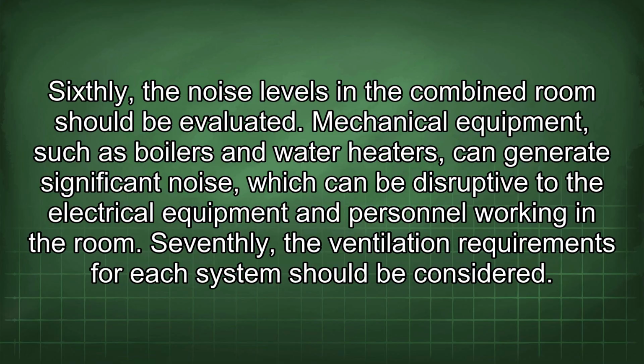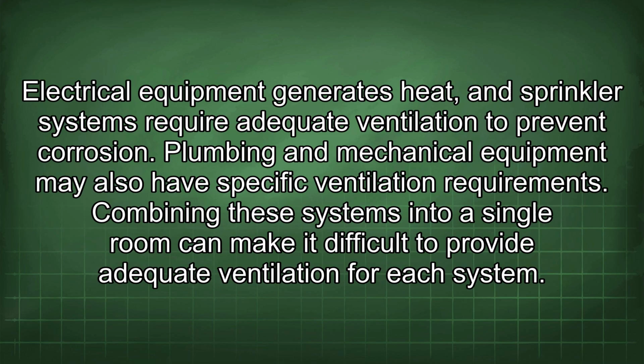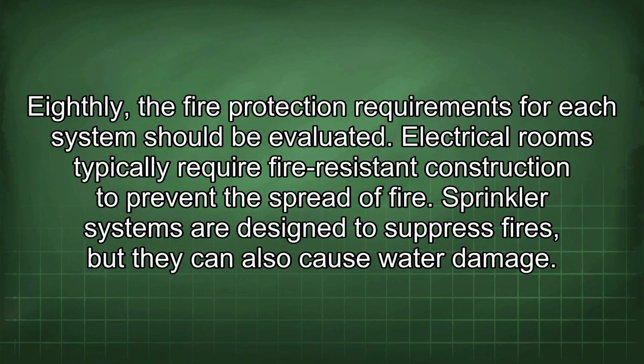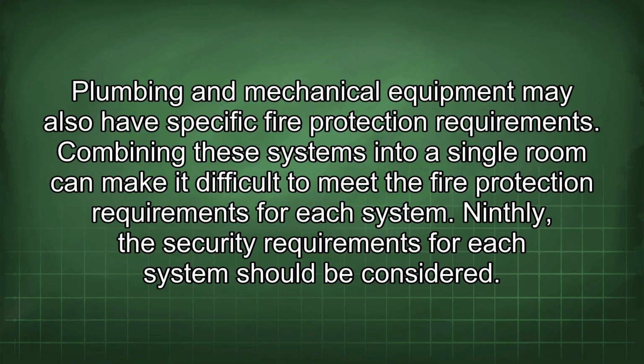Seventhly, the ventilation requirements for each system should be considered. Electrical equipment generates heat, and sprinkler systems require adequate ventilation to prevent corrosion. Plumbing and mechanical equipment may also have specific ventilation requirements. Combining these systems into a single room can make it difficult to provide adequate ventilation for each system. Eighthly, the fire protection requirements for each system should be evaluated. Electrical rooms typically require fire-resistant construction to prevent the spread of fire. Sprinkler systems are designed to suppress fires, but they can also cause water damage. Plumbing and mechanical equipment may also have specific fire protection requirements. Combining these systems into a single room can make it difficult to meet the fire protection requirements for each system.